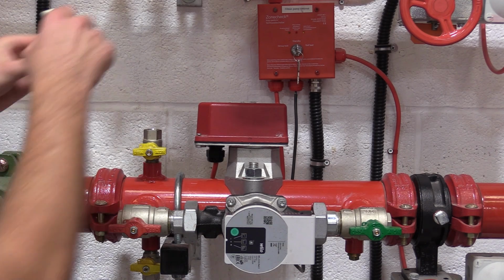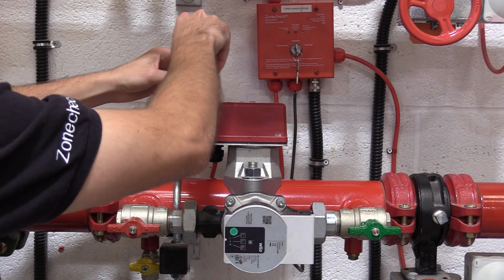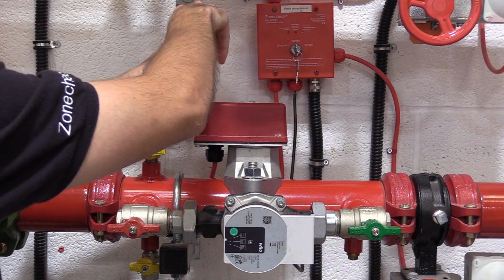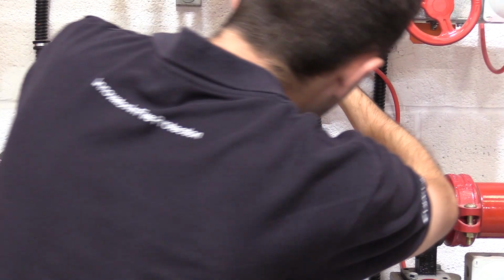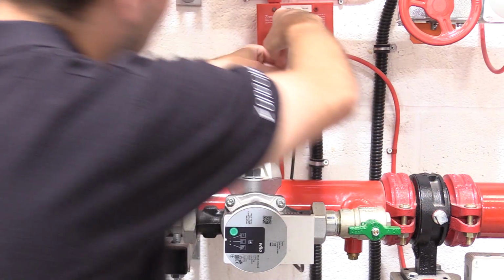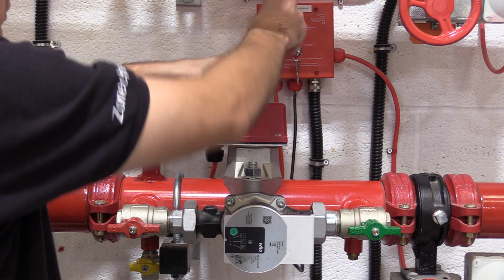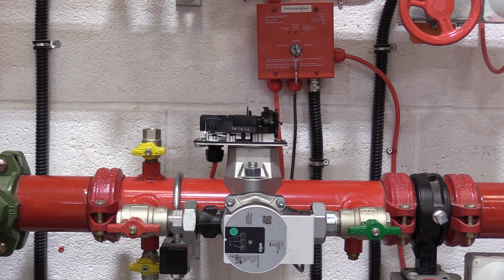Let's check the flow switch by removing the lid. Zonecheck is supplied with a special Allen key to remove the two Allen bolts at opposite corners of the flow switch lid. If this tool is not available, then a standard small flathead screwdriver is normally sufficient.